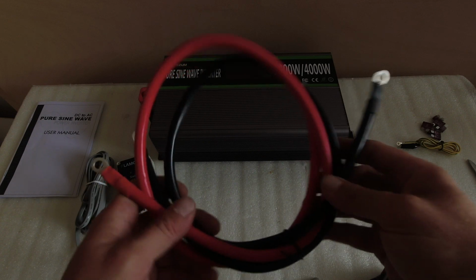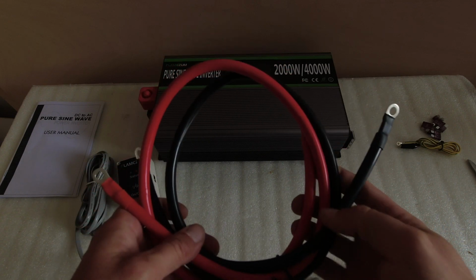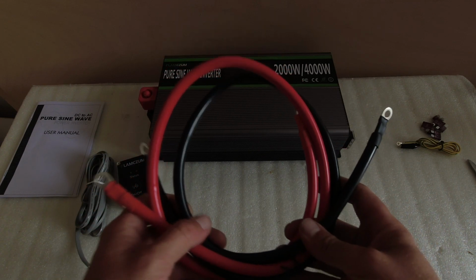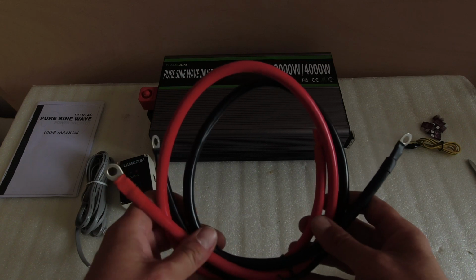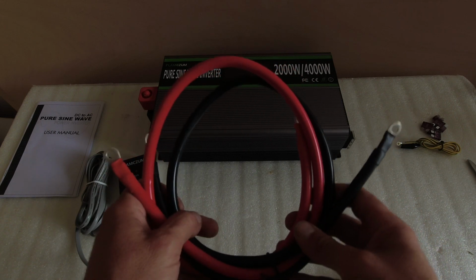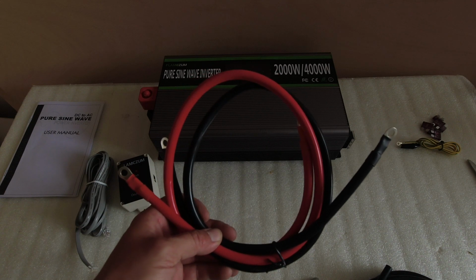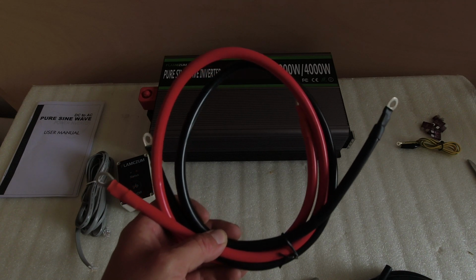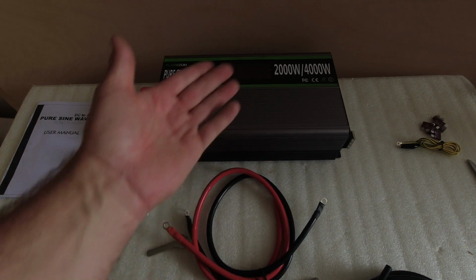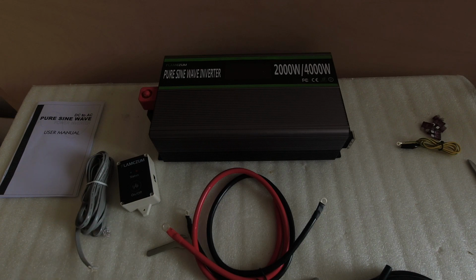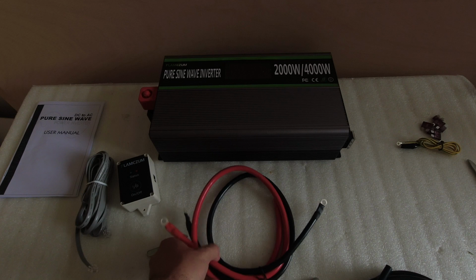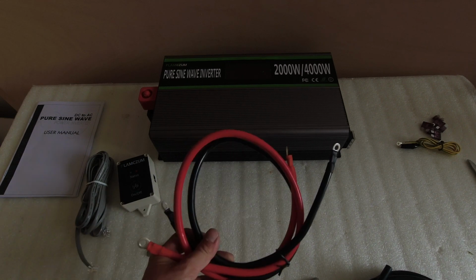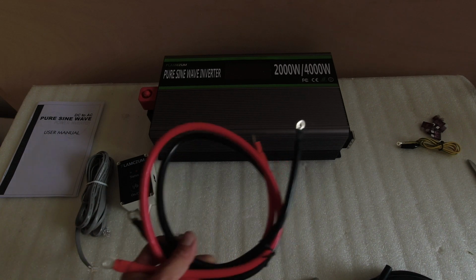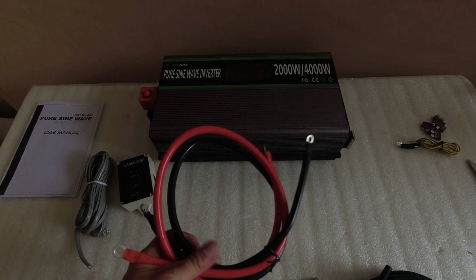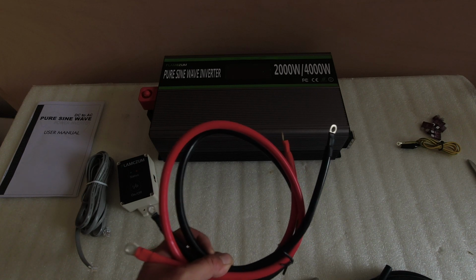For this test I will use these cables, but when installing in our camper van I will use 35 square millimeter cable to connect the battery and the inverter, because the inverter is 2000 watts divided by 12 volts, which means 166 amps, and the 35 square millimeter cable can carry up to 180 amps.